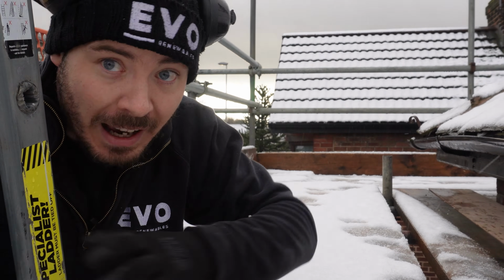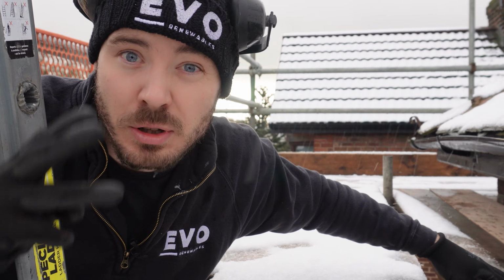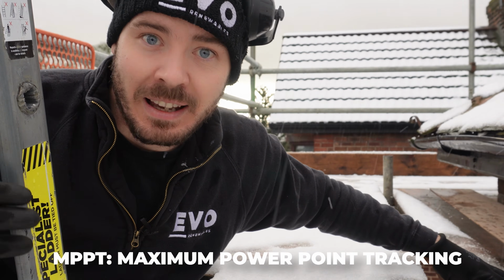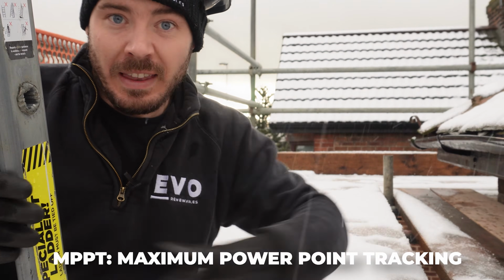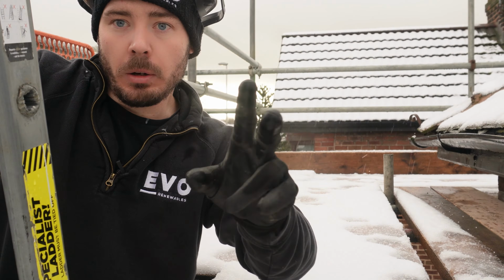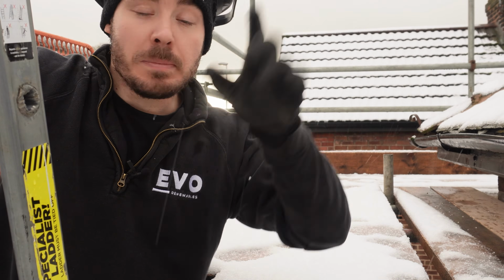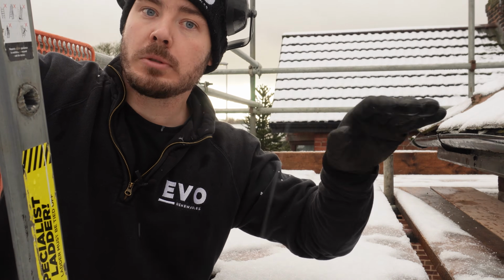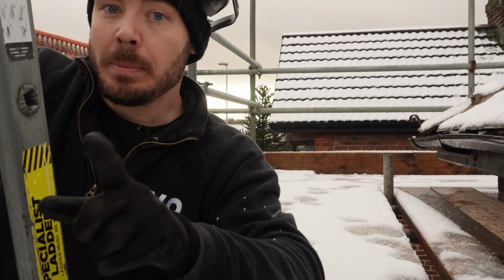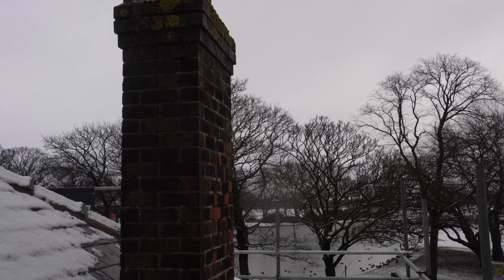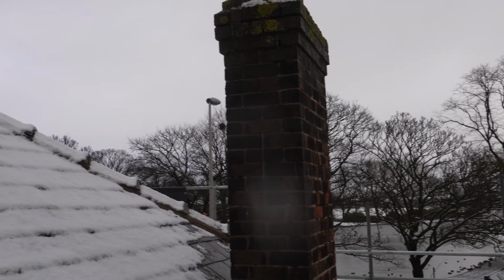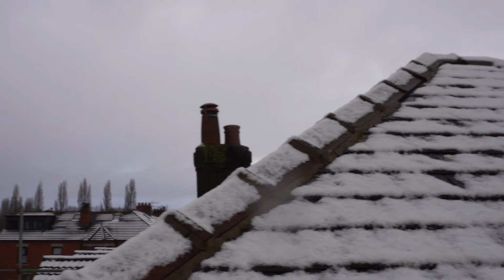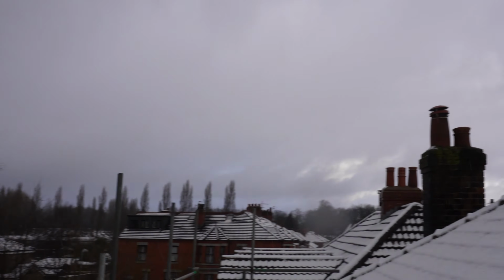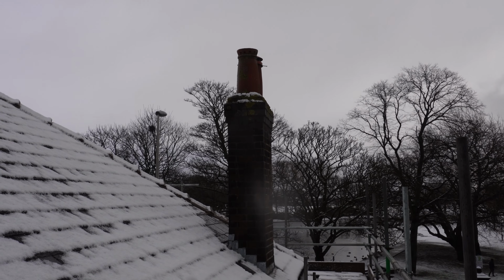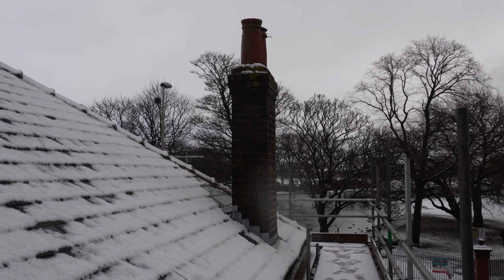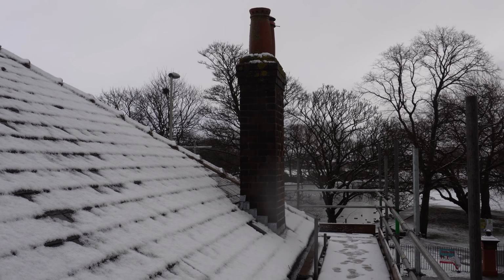So most inverters have 2, at most 3 MPPTs, and they're maximum power point trackers. And that's really the input for the solar DC. With the SolarEdge, because it has the optimizers underneath each panel, it means we can install them on multiple orientations because the MPPTs are panel level monitoring. One of the beauties with SolarEdge is, unlike a conventional string system, it allows you to let every panel work to its own maximum. Because it's got the panel level MPPTs, shading doesn't really affect the whole array, it only affects the panels that have shading on.